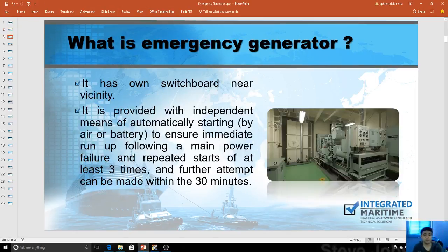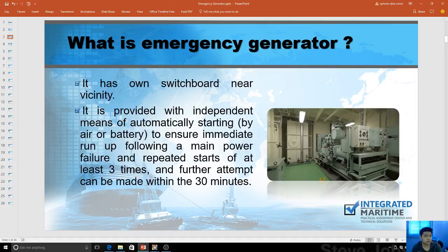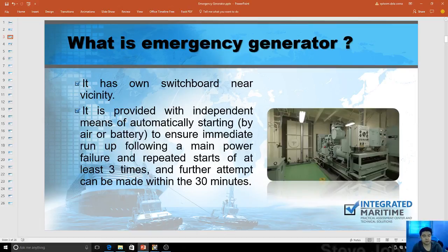It has its own switchboard near the vicinity, inside that specific room. It's provided with independent means of automatically starting by air, battery, or hydraulic, to ensure immediate running. Upon main power failure, repeated starts are attempted at least three times. In the board exam, this came up — how many starts does a generator get? If using air, you have an emergency air compressor inside, and further attempts can be made within 30 minutes. That's a port state requirement.